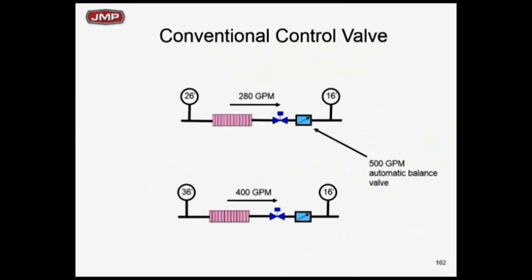What is the flow limiter doing at 400 GPM that you picked for 500? Nothing. There's not enough differential pressure across the spring to make it work. It's sitting there deaf, dumb, and happy. That flow limiter is not going to do anything until you get to 500 GPM. That automatic balancing valve is not even going to start functioning until you get to 500 GPM. So now I've jumped from 280 to 400. Load didn't change. Differential pressure changed. I lost delta T control.